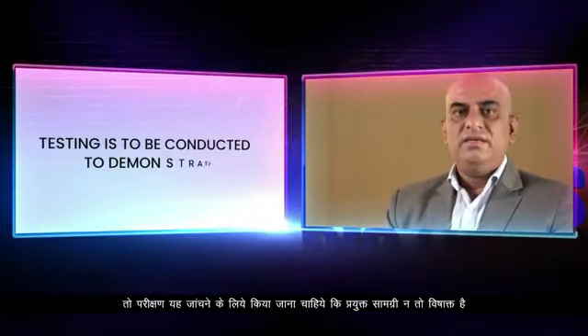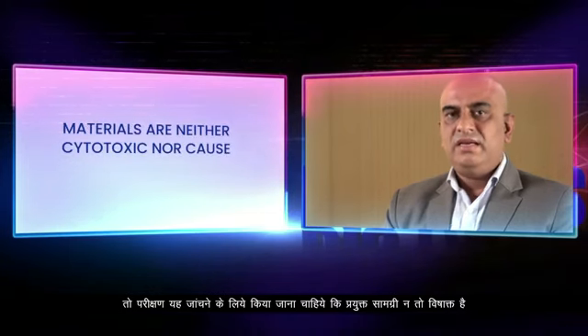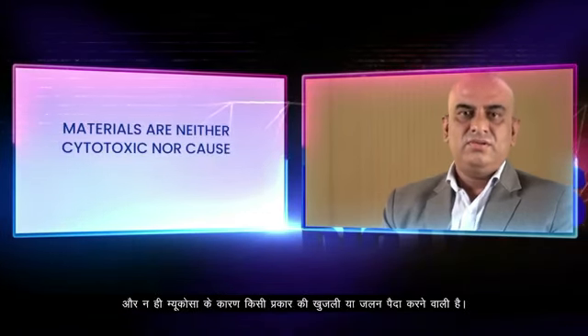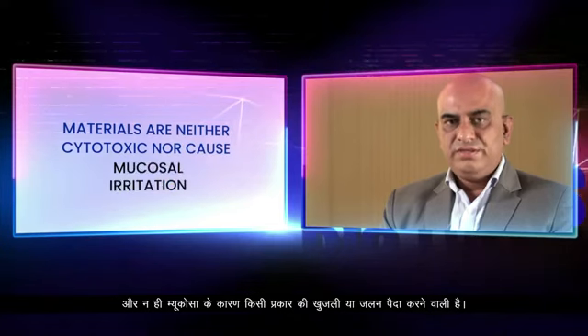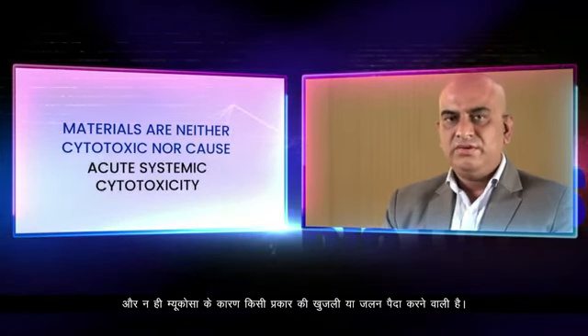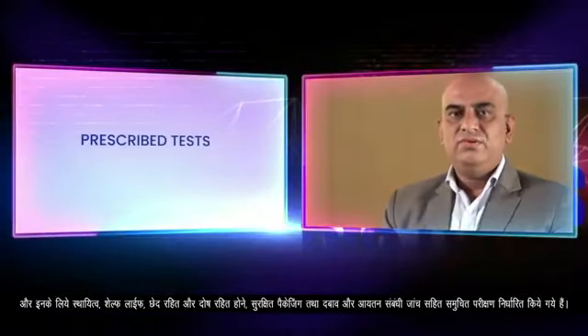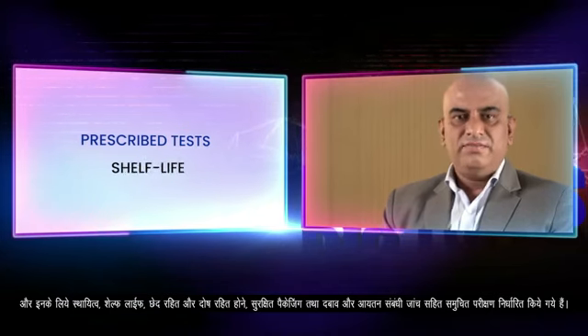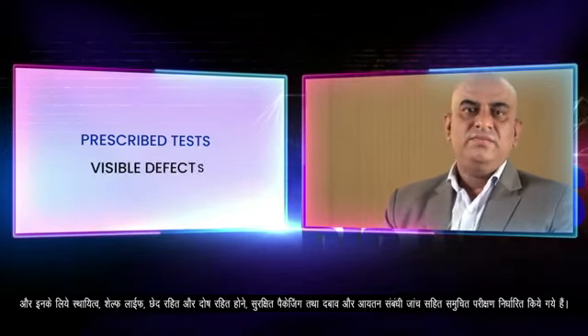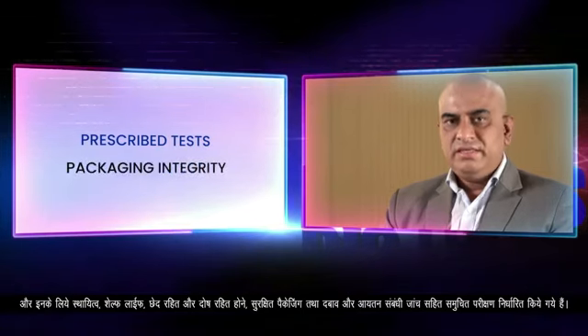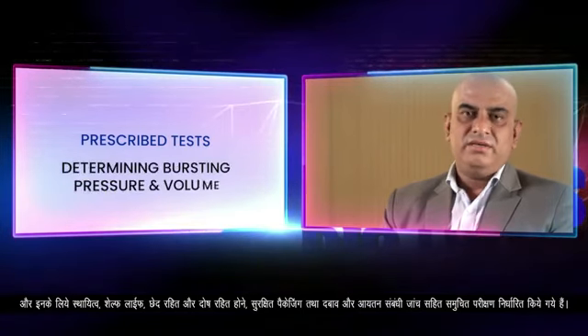Since the female condom is in repeated contact with surface mucosa and possibly compromised tissue surfaces, the testing is to be conducted to demonstrate that the materials are neither cytotoxic nor cause sensitization, mucosal irritation or acute systemic cytotoxicity. All these issues are addressed in this Indian standard, and it prescribes tests including those for stability, shelf life, freedom from holes, visible defects, packaging integrity, and determining bursting pressure and volume.